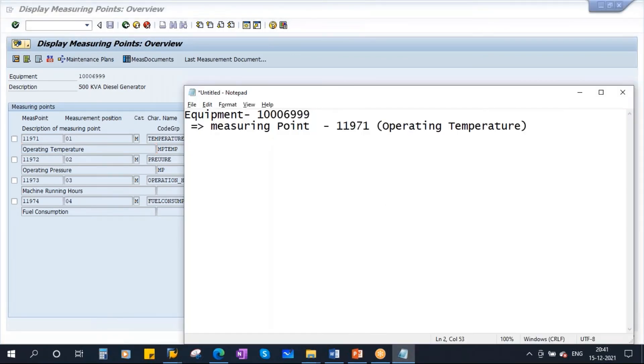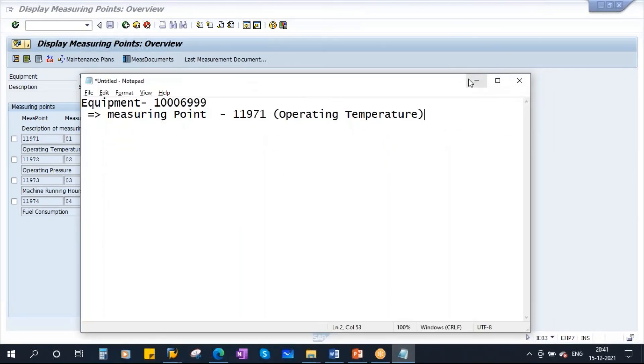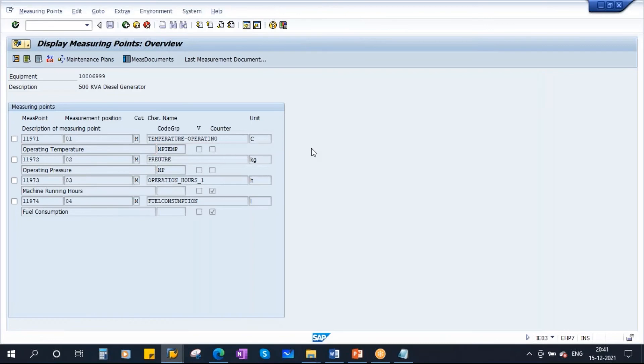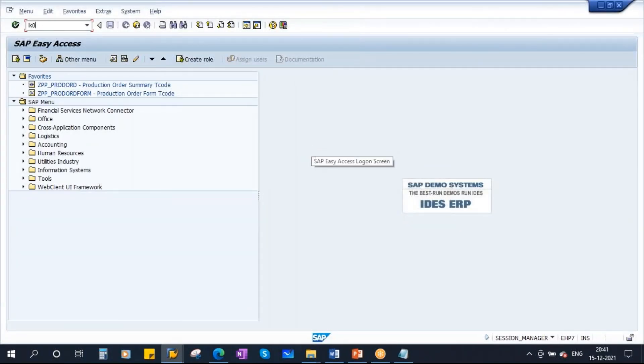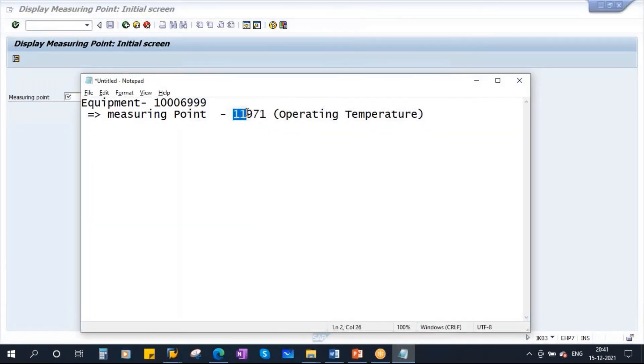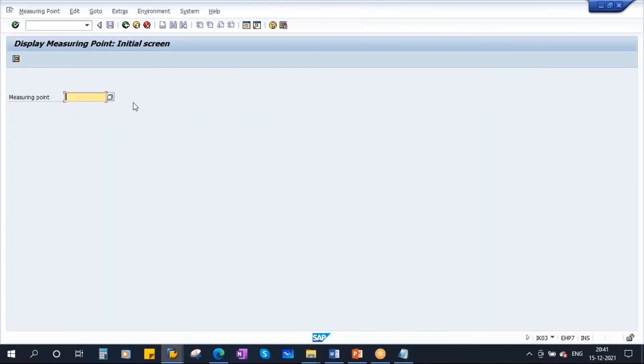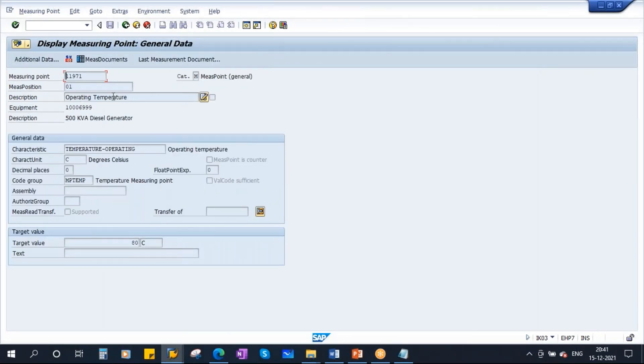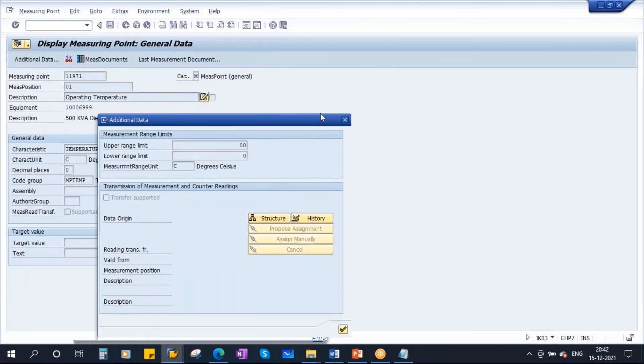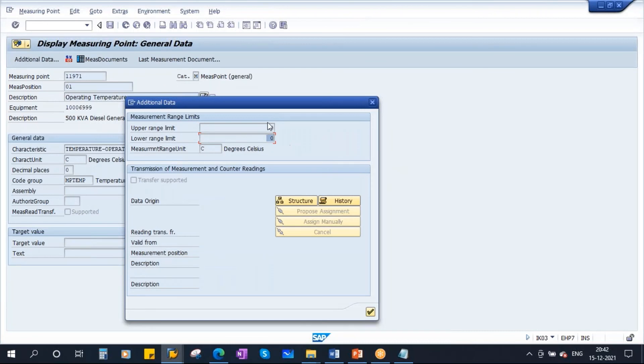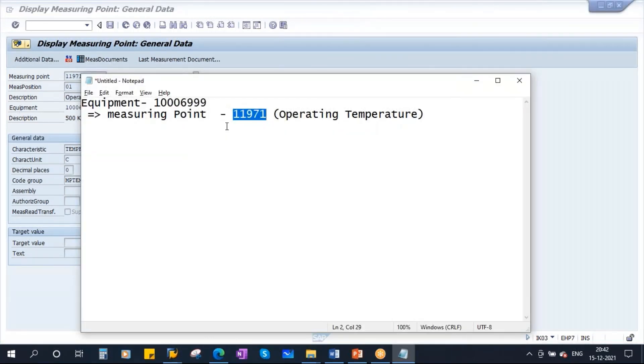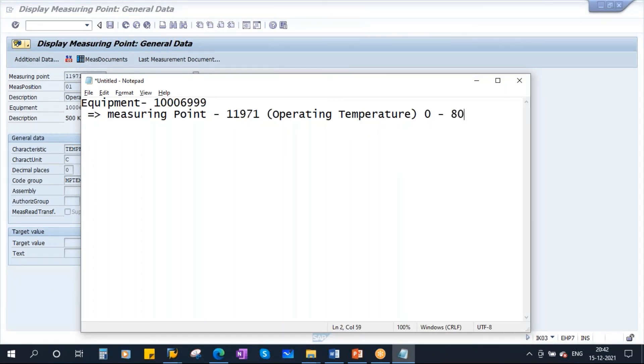This was already created in our previous sessions. It will have limits. I will go to transaction IK03 to show the measuring point 11971. If you go to this measuring point and click on additional data, you see the limits: lower limit is 0 and upper limit is 80. The expected values are from 0 to 80 degrees.